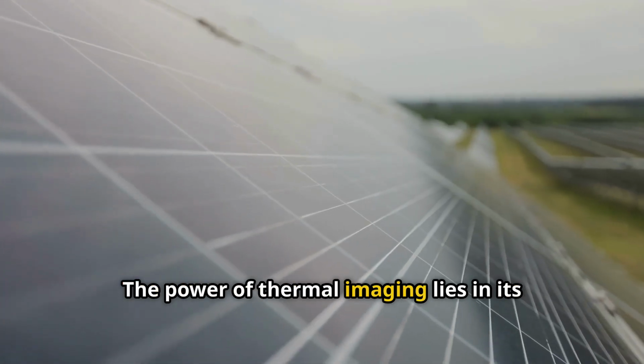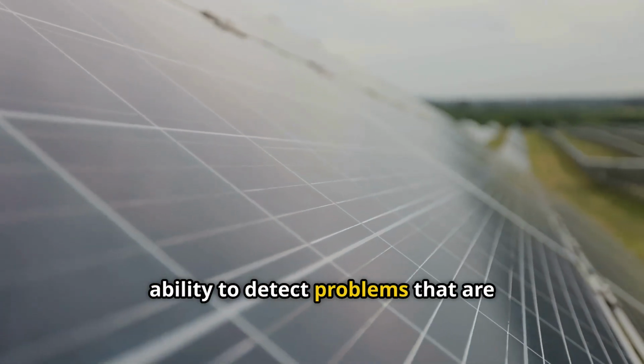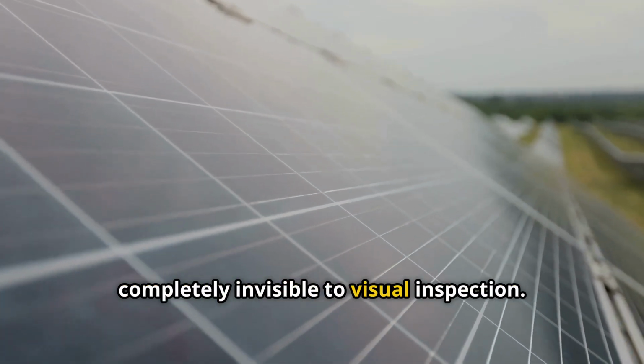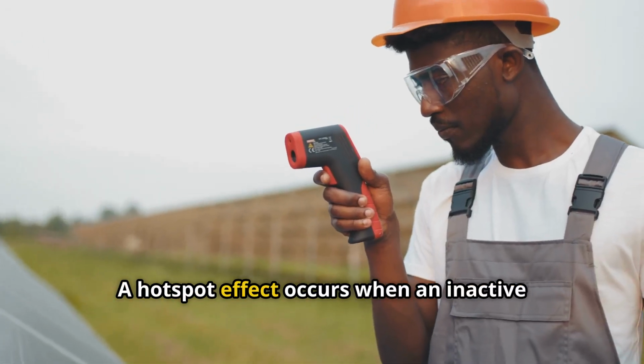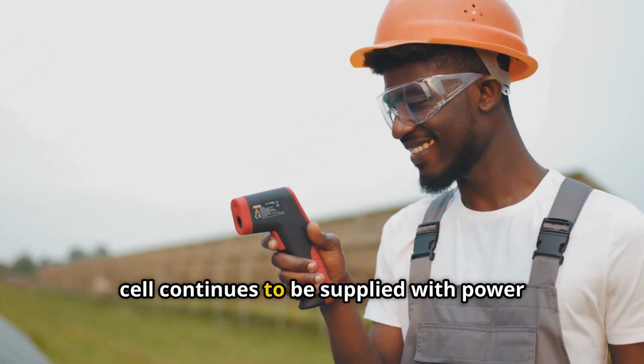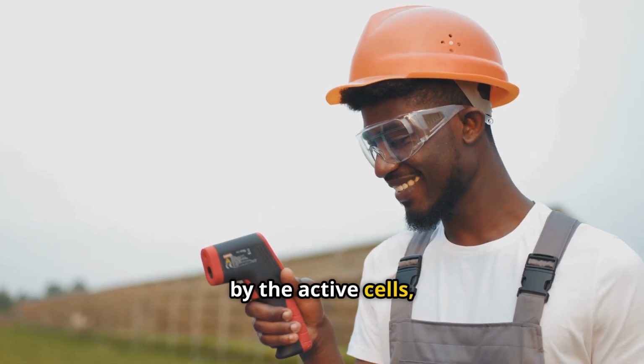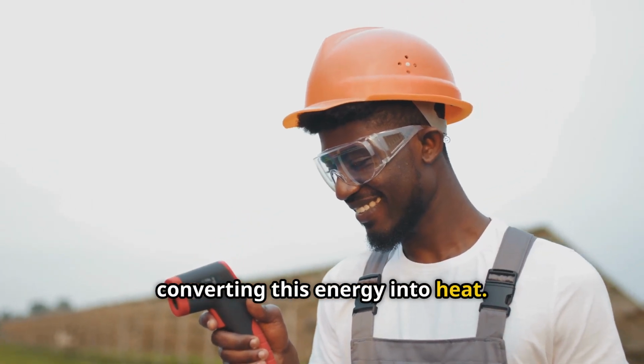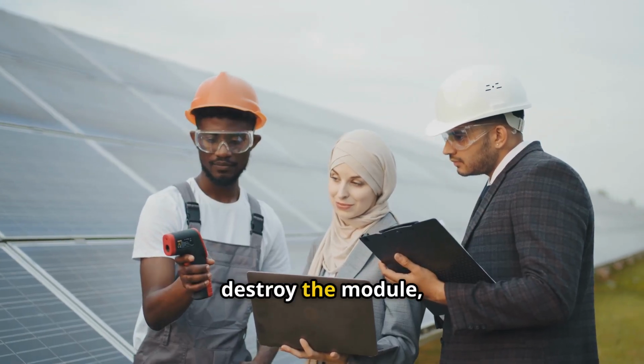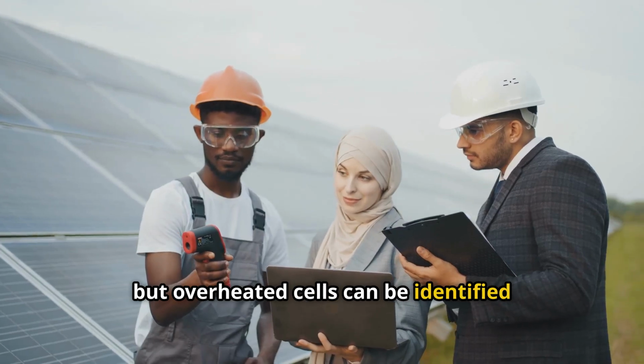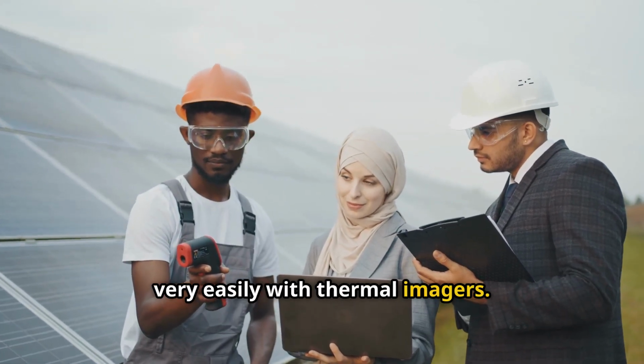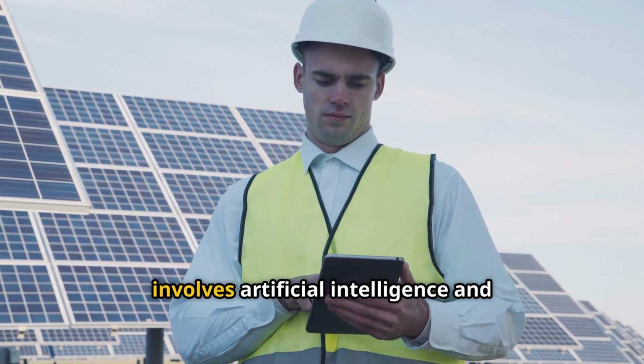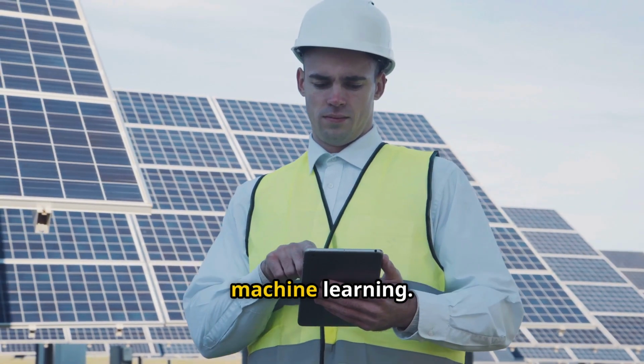The power of thermal imaging lies in its ability to detect problems completely invisible to visual inspection. A hotspot effect occurs when an inactive cell continues to be supplied with power by active cells, converting this energy into heat. These resultant hotspots could even destroy the module, but overheated cells can be identified very easily with thermal imagers.